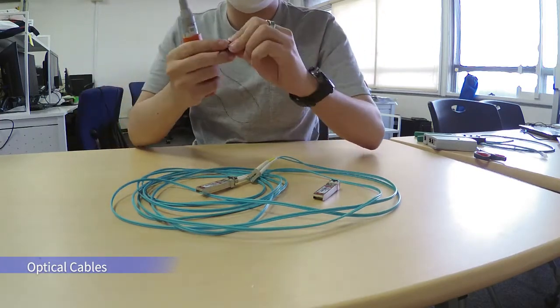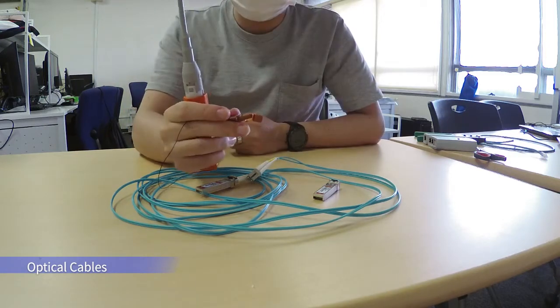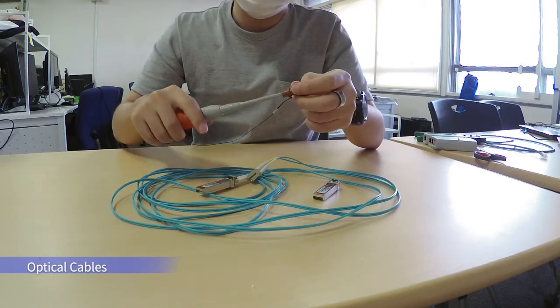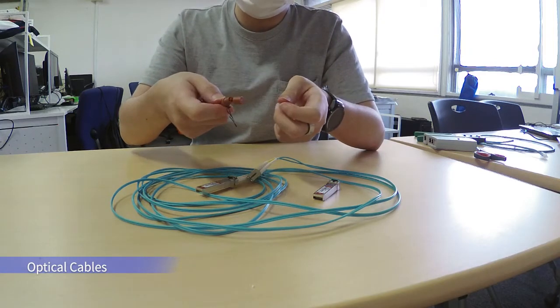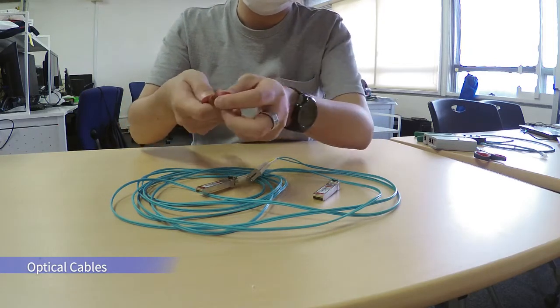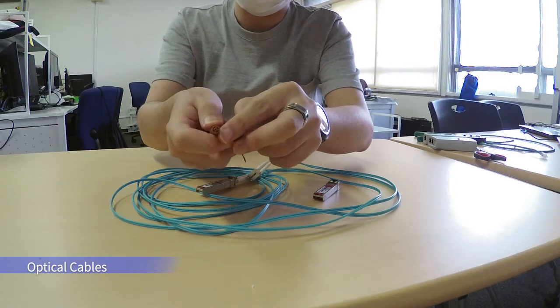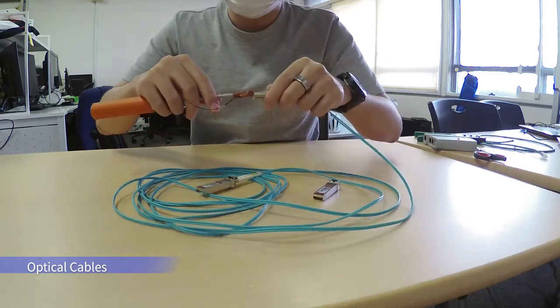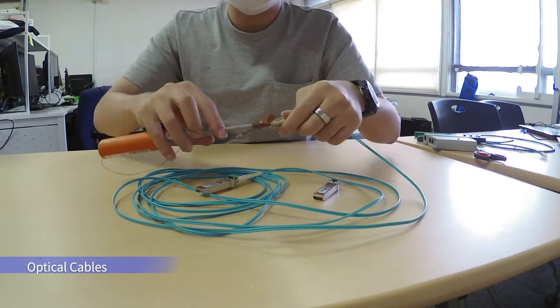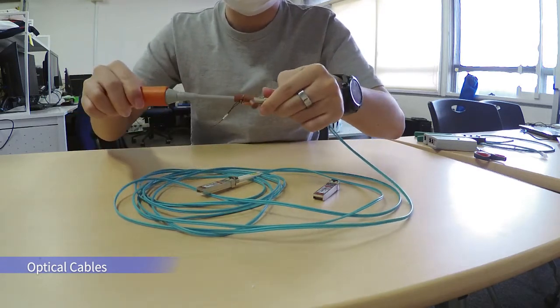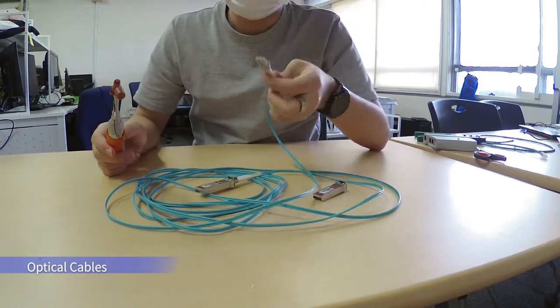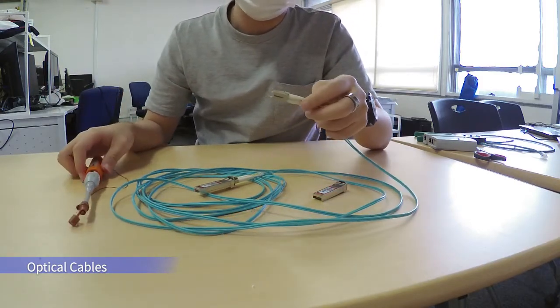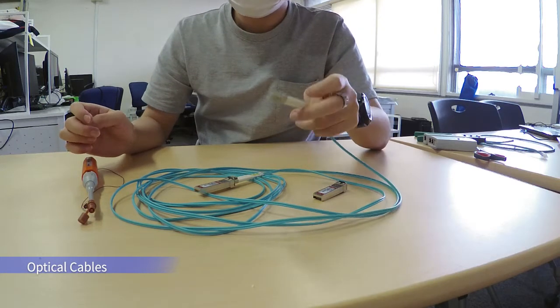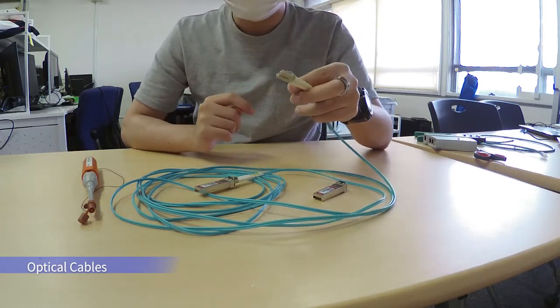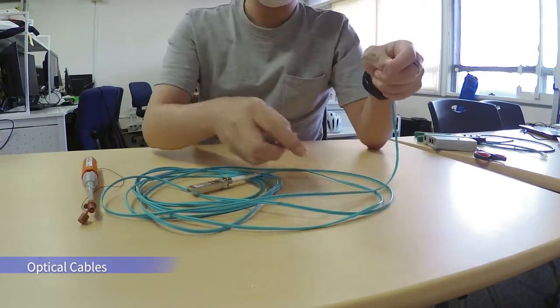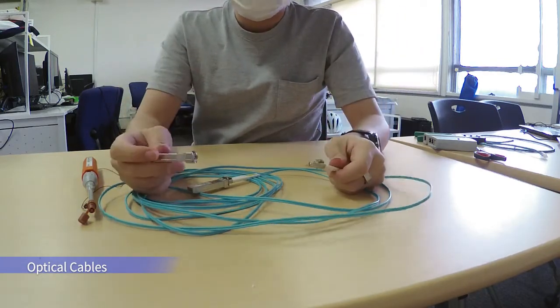On the other hand, I'll explain the way to polish the fibers. As we checked before, this cap has two levels. Remove only the first cap like this. And when the cap is removed, you can stick in the fiber tip like this. Then push the polisher to polish the fibers. Now I push it 3 times, but in fact, you don't need to do it 3 times. This is how to polish the fibers. Now both the fibers and the module are clean.